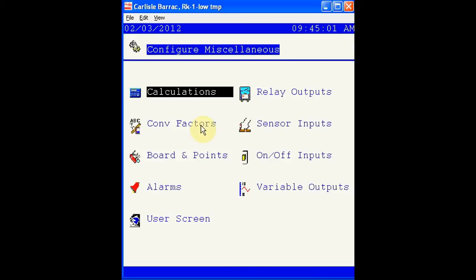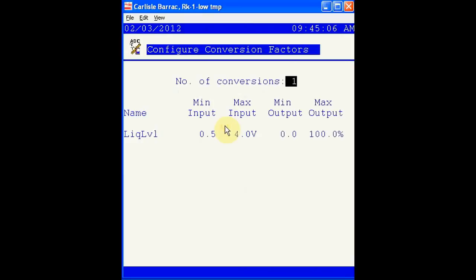Conversion factors can be used to set sensor types not already available in the 255. In this case, you see a liquid level was utilized that did not already exist in the 255 controller. The installer knew that the minimum input for this liquid level transducer would be 0.5 volts DC and the maximum input would be 4.0 volts DC, corresponding with 0% or 100%. This liquid level name was defined and then selected out of the sensor type list in the rack.